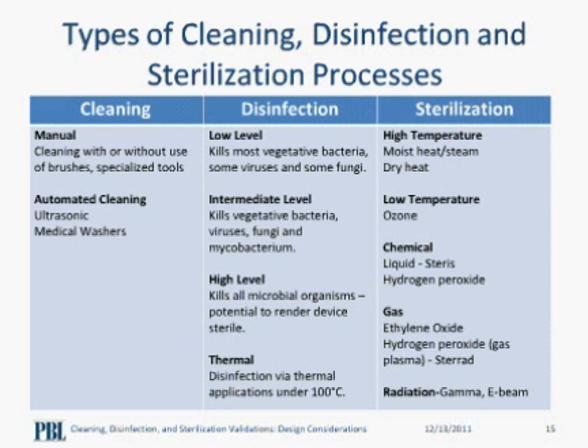This next table presents the different types of reprocessing procedures we have discussed. There are 2 methods of cleaning: manual, which is cleaning with or without use of brushes and specialized tools. If your device is complex and requires meticulous cleaning, you may want to consider designing specialized cleaning tools for your device. The second cleaning method is automated cleaning with the use of ultrasonic and medical washers.